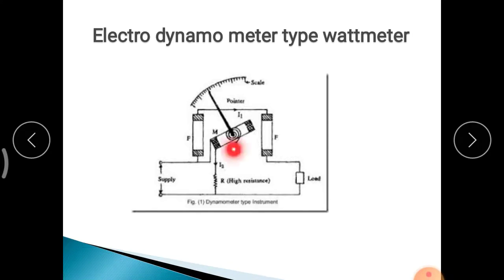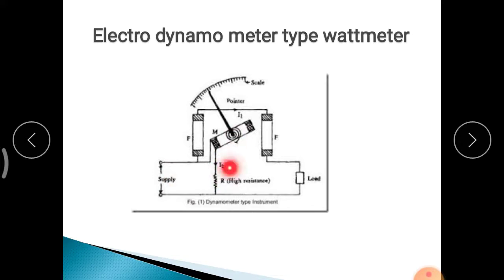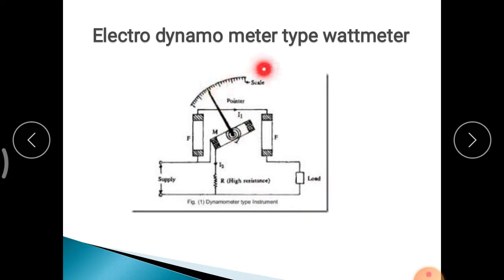The moving coil is placed in between the two fixed coils and is connected across the supply, carrying current I2. Resistance R is connected in series with it to limit the current. It also consists of a pointer connected on the spindle of the moving coil, with springs providing the controlling action, and a scale.